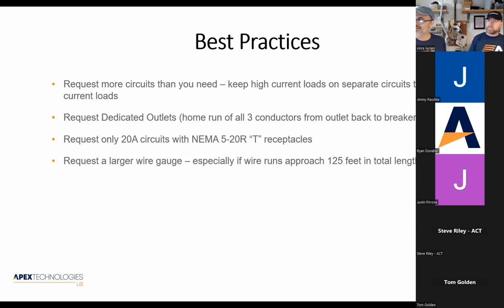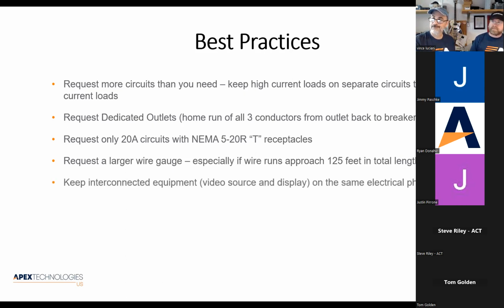And I wrote in here 125, absolutely. But if you're at 90, if you're at 100, go ahead and ask for the larger wire, right? There's no code restriction to using a larger wire. You just can't use a smaller wire. Okay. Kind of similar to that question we had earlier about outlet size and circuit. Yeah. So this is just kind of good practice.